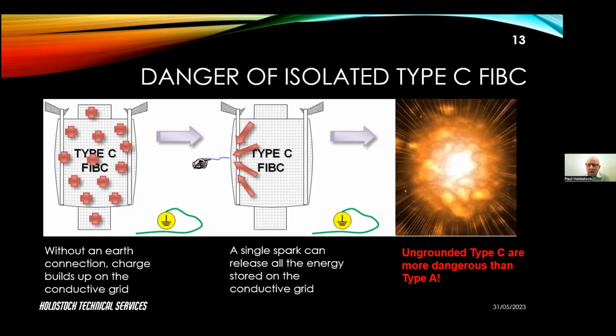And that is now the conductive path to Earth. So all the charge now that's built up on the bag and on that conductive grid will very quickly be transferred into that spark gap. And that will release a very large amount of energy. So all the energy that's stored on that bag will come off in a single spark, and that will almost certainly ignite any flammable gas or vapor present, and will ignite most combustible dust as well. So an ungrounded or an isolated type C are actually far more dangerous even than a type A with no static protection, because all that energy is being released. And it's very likely then, if you're operating in a hazardous area, that an ignition will occur.